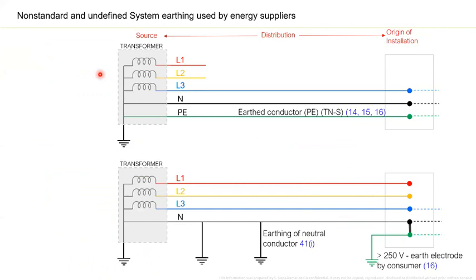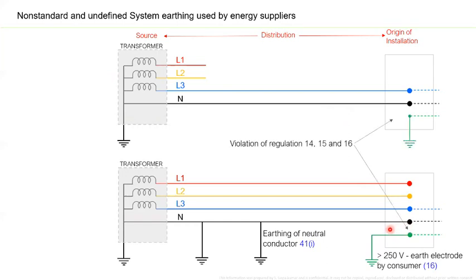But as I said in my first presentation, you can see here where I'm moving the cursor, the earthed conductor is missing in our distribution. The electricity supplier is not providing any earthed conductor. As a result, the link between the neutral and earth is also missing in a TN-C-S network. So basically, the network becomes a TT network.